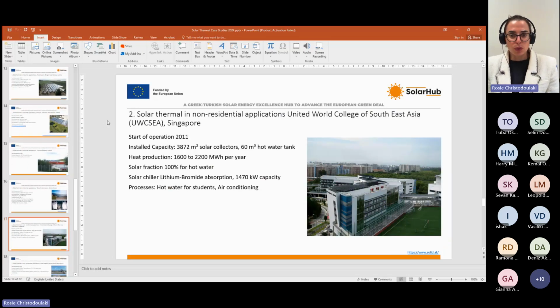Now we start to present the applications in non-residential premises. So the first one is in Singapore, in the United World College of Southeast Asia. This is a solar thermal system installed in 2011. The capacity is approximately 4,000 square meters of flat plate solar thermal collectors. And also, this heat is stored in a total storage capacity of 60 cubic meters.